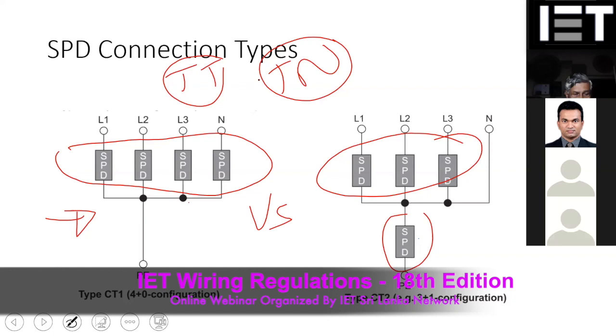Short circuit. Okay, if I give a hint, whether you use the SPD before the RCD or after the RCD, what is your recommendation? Whether to use the SPD before the RCD or after the RCD? Before the RCD. Okay, so if I use the first arrangement before the RCD, what will happen in a TT? So you can see, for example, if there is a fault in one SPD, what will happen?